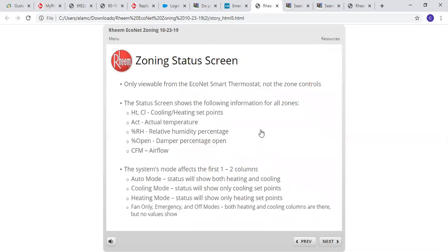So we're going to go in here. The zoning status screen is only viewable from the Econet smart thermostat, the primary zone 1 thermostat, not the zone controls. In the status screen, it shows the following for all zones: heating, cooling, set points, actual temperature, relative humidity percentages, percentage damper open, also your CFM and airflow. The system's mode affects the first columns 1 and 2. Auto mode will show both heating and cooling. Cooling mode will show only cooling set points. Heating mode will show only heating. You also have fan only, emergency, and off modes.